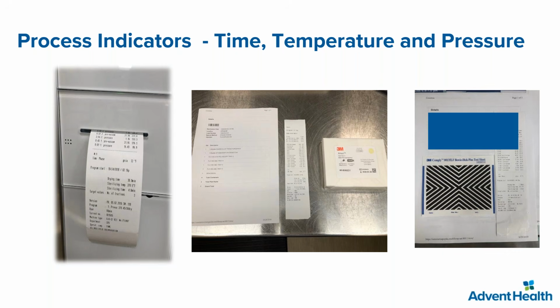Okay. And then we add another test, what is called the Bowie-Dick test, that is going to measure what? It's going to measure how well that sterilizer removes the air from the chamber, and whether the penetration of the steam was properly made. This is the one from 3M, the one that you see in the center. It's like a package, like a little cube. When the process finishes, you open it, and this is what you are going to find. You have to see that every single line has to be completely black. That's telling me that the air was taken out from the chamber in a proper manner, and that the steam that was utilized in that steam sterilizer penetrates correctly all the pouches and all the trays that were inside.